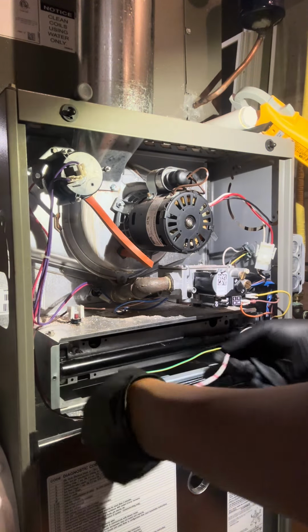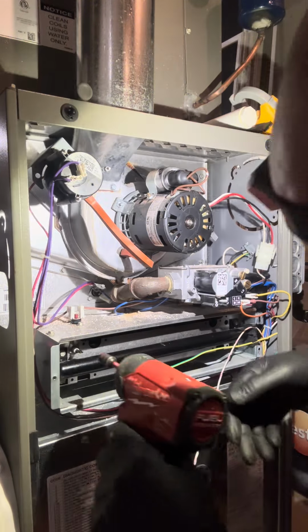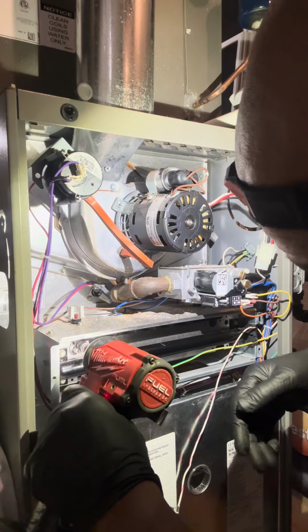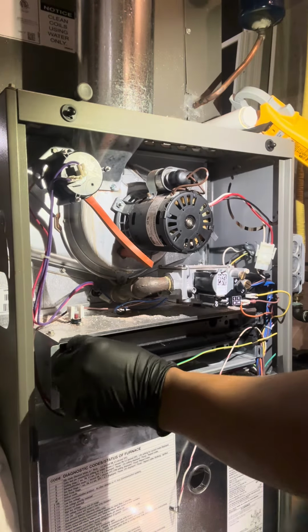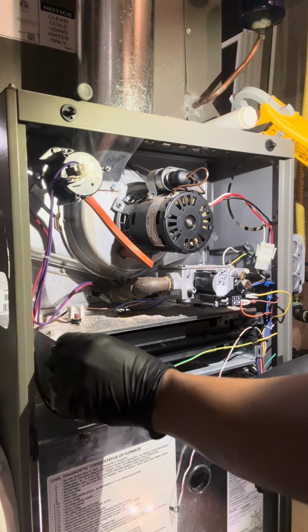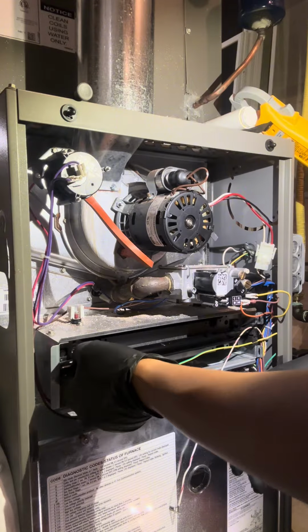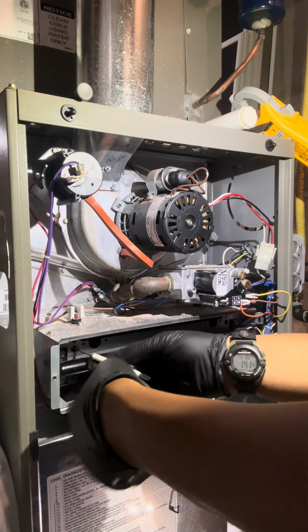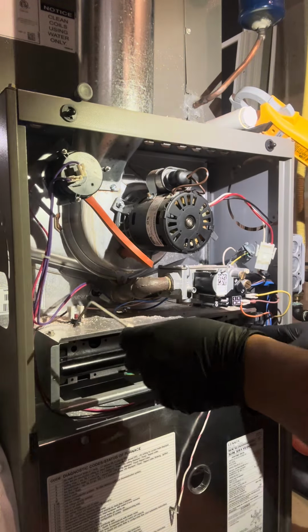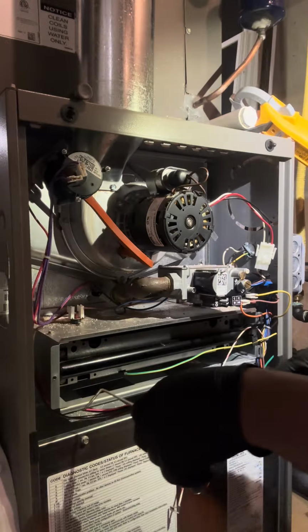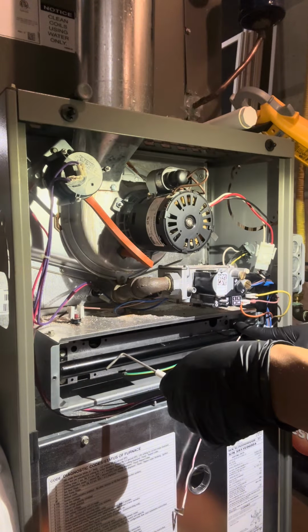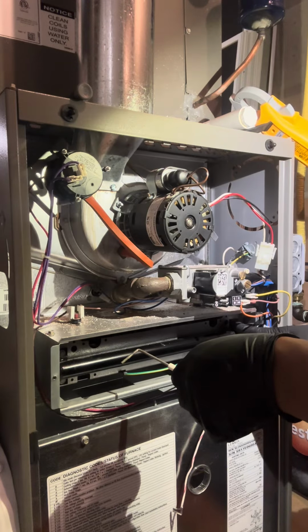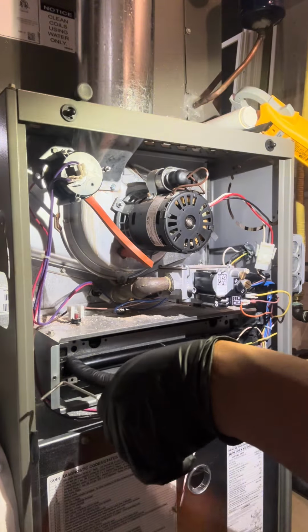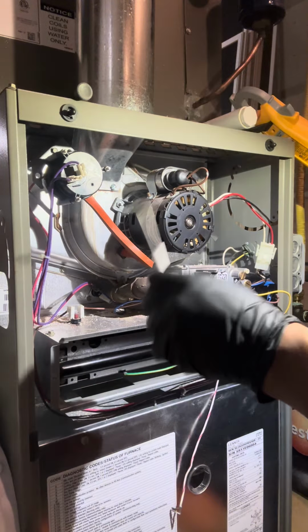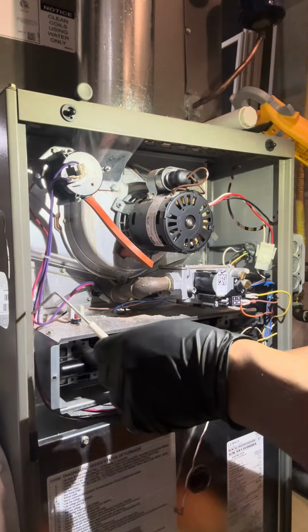This flame sensor sits inside the flames, and the job of the flame sensor is another form of a safety. Its main job is to prove that the flames are making it all the way across. Your flames start here on this side, and with your hot surface igniter, it shoots all the way across, and this just proves that the flame made it all the way across.